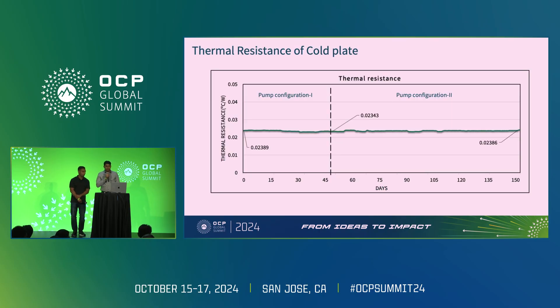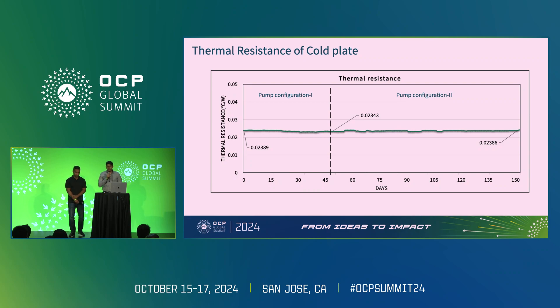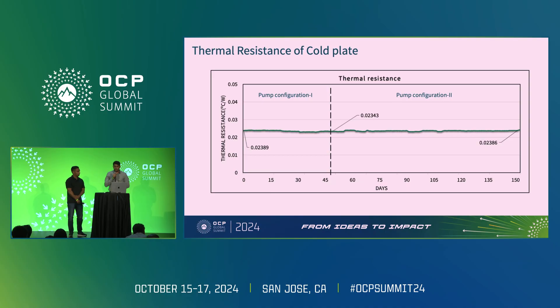Upon the findings from the experiment, we ran the experiment for a total of 150 days. On day zero, the thermal resistance of the cold plate on average was around 0.0238°C/W, and at the end of testing we saw the thermal resistance was around 0.02386°C/W. The thermal resistance was constantly stable throughout the 150 days of testing. There were fluctuations of around less than 0.01°C. We can say that at high flow rates, even for 150 days of testing, the thermal resistance did not change and was quite stable.